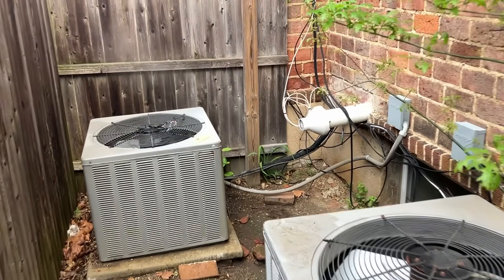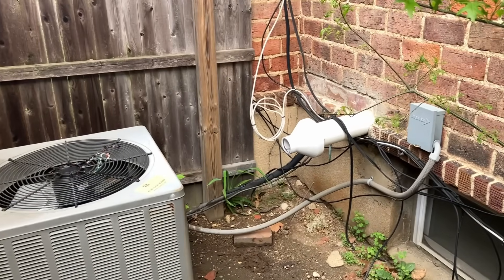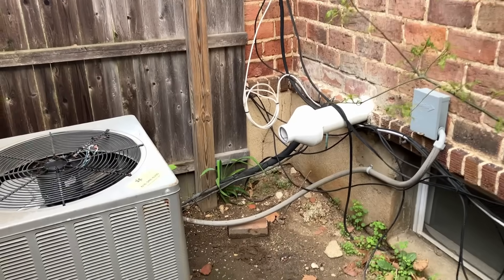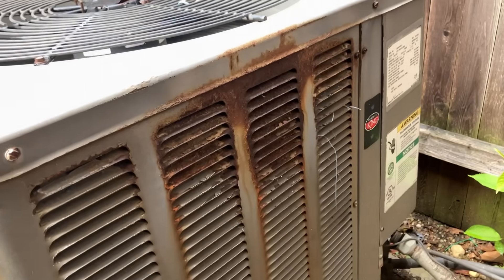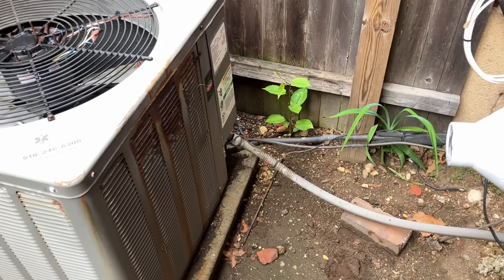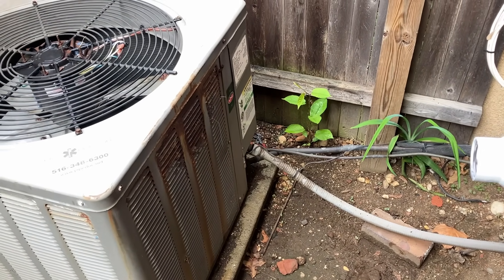What's really crazy is we have this concentric vent kit from the condensing boiler that's in the basement, and it's discharging right into the side of this two-and-a-half ton outdoor condensing unit. Talk about poor planning.